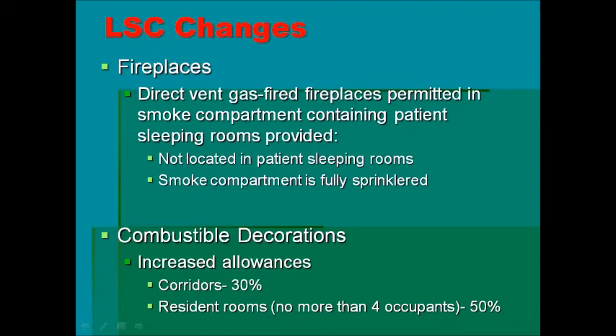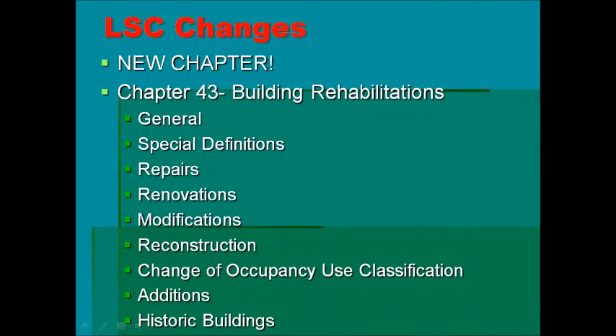There are some requirements for fireplaces where they can be in the patient care area, provided the rooms are fully sprinklered and they're not located directly in a patient sleeping area. And when it comes to those combustible decorations, under the newest edition of the code that's enforced by CMS and most jurisdictions, you are allowed to have combustible decorations in your corridors up to 30% of wall space and up to 50% space in a resident room that doesn't serve any more than 4 occupants, providing that the building is sprinklered and so on and so forth. The reality is this: we don't want to see that volume of combustibles in your building, but you've got to balance the reality of it with safety and understand that there are some provisions that allow that.